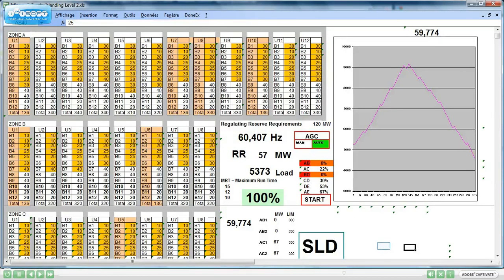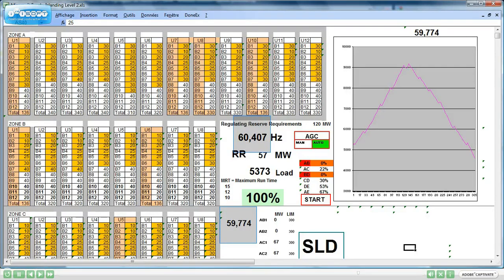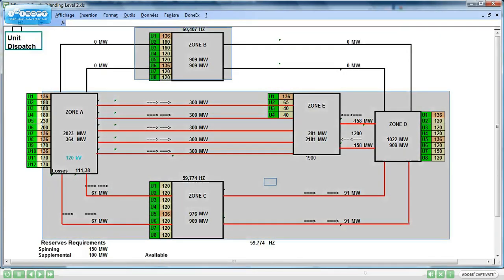We are just there. There are two frequency indications. One at 60.407 Hz and the other at 59.774 Hz. What do you think we are having? Yes, there are islands.